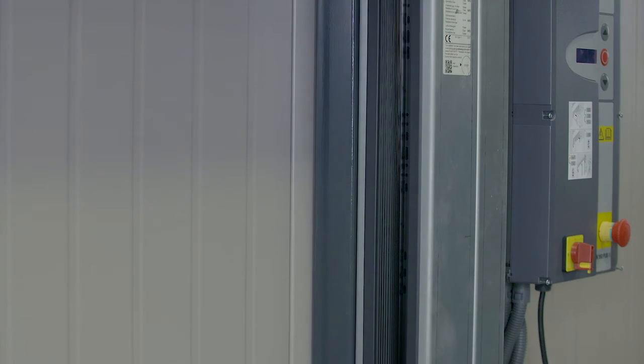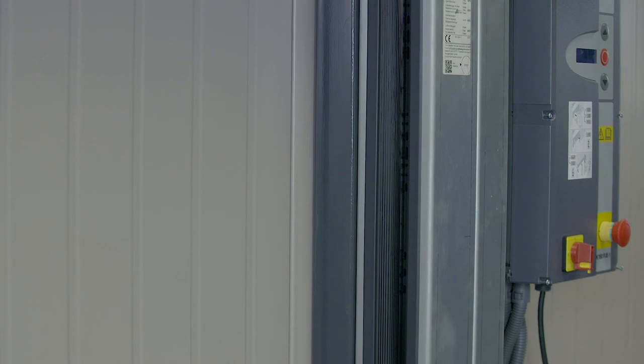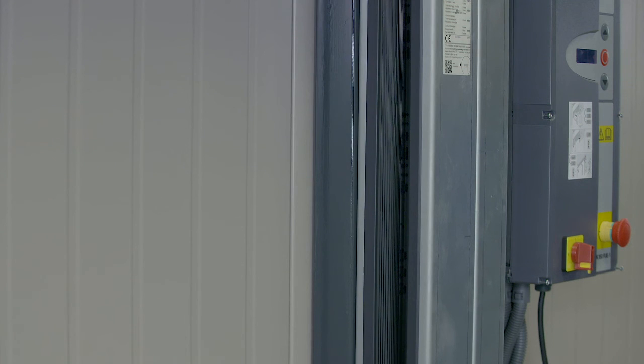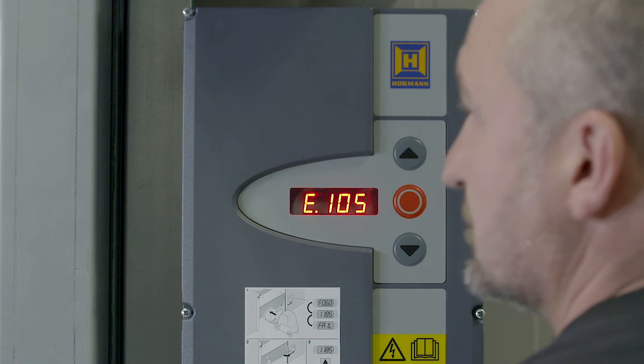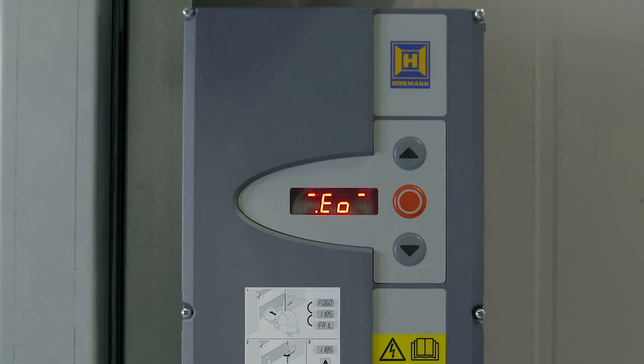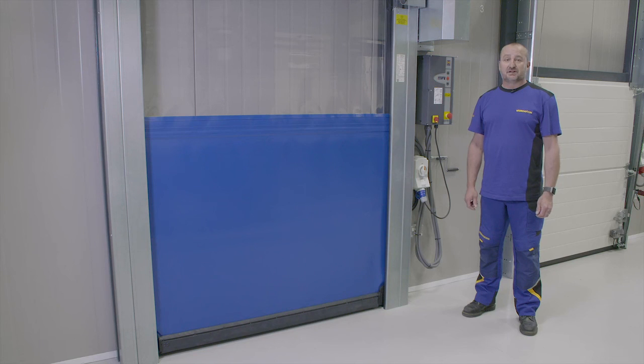Finally, run the door and break the light grid. The door should reverse to the top limit and give you the input E105. The door is now back into normal operation.